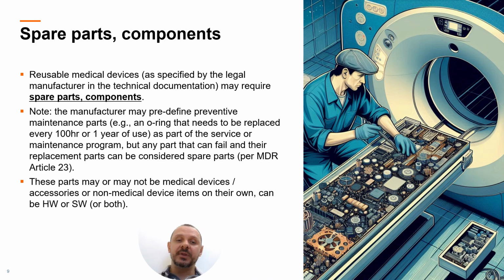It is important to point out that a part can only be considered a spare part or a component if it is not significantly changing the device. And the definition of what a significant change means is defined in Article 23. If we change something in a device, a part that would alter the clinical intended use or the risk profile or certain other defined restrictions, then the whole configuration should be considered a new medical device and a separate conformity assessment needs to be performed.